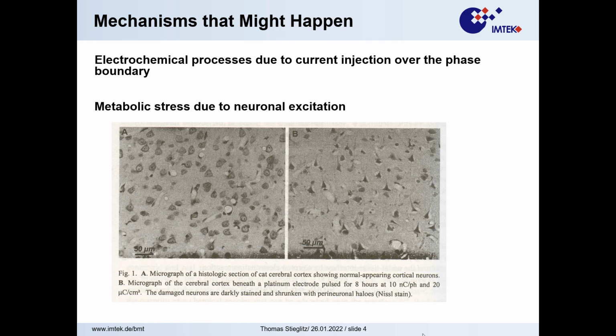So you did everything you should do as an engineer. You stay below the limits. 8 hours, it's not that much, right? If you had a cochlear implant, you would probably want to hear more than 8 hours a day. Yeah, but it doesn't look good. 10 nanocoulombs per phase is now an important parameter, but it does not help a lot. We don't know at this point how much current, which pulse width. We see it's 20 microcoulombs per square centimeter, but we have no idea how large the electrode was. So did it cover the whole cortex? Was it a needle with a tip or something like that? That means we have the parameters I told you you should look at, but we still have some missing information.